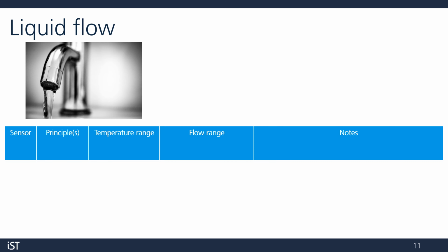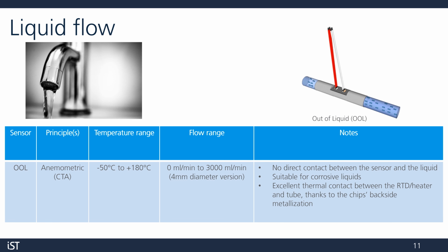Finally, if you're working with liquids like water or chemicals, you might want to take a look at our out-of-liquid, or OOL, flow sensor. Using the same measurement principle as the FS7, this sensor can measure the flow speed of most liquids. Just like the FS7, it consists of a heater and a temperature sensor, and they're soldered on the outside of a stainless steel tube, and there's no actual contact with your fluid flowing through the tube.